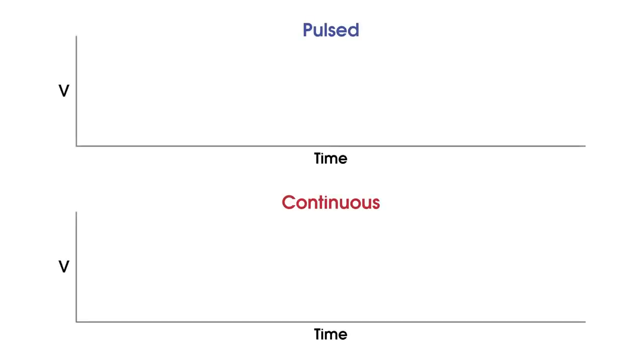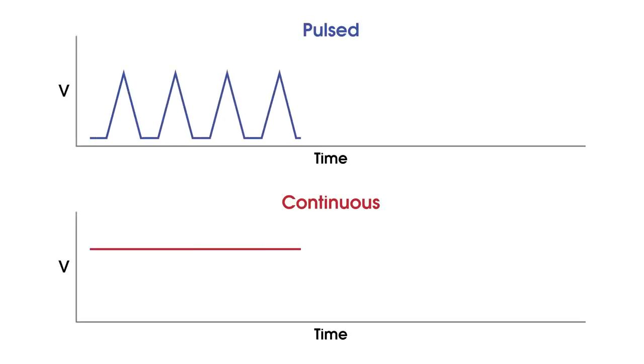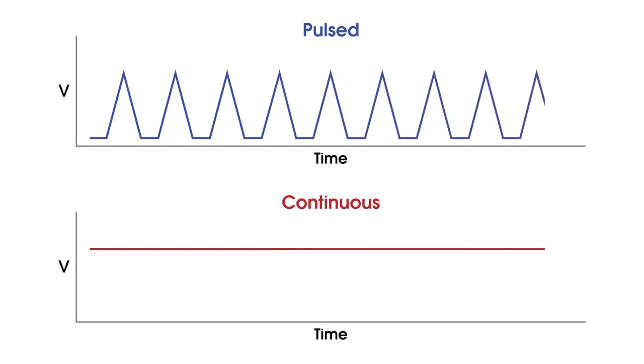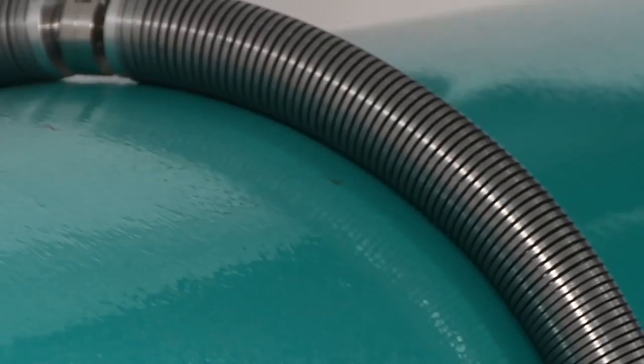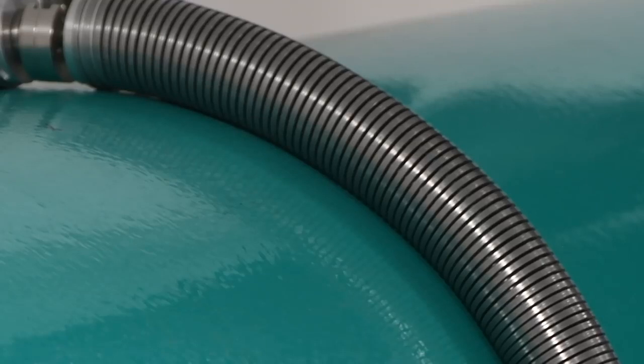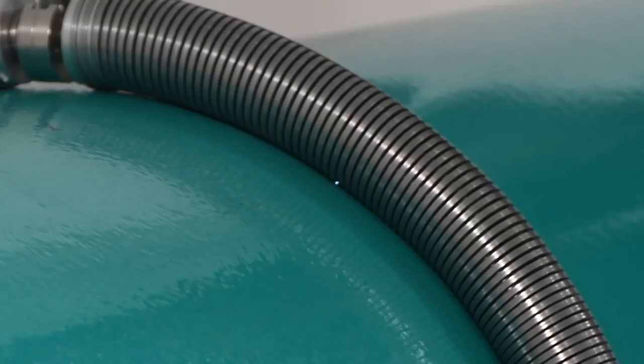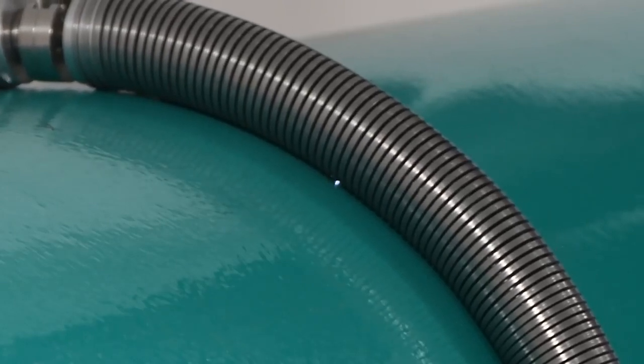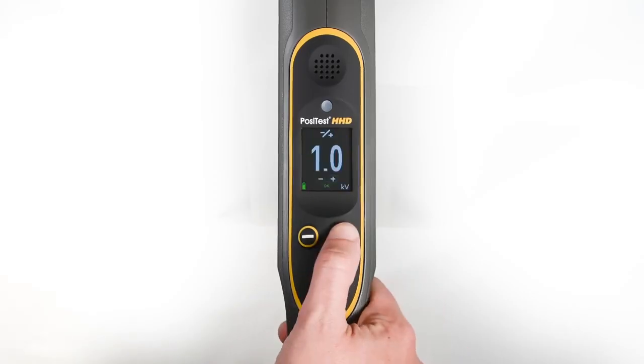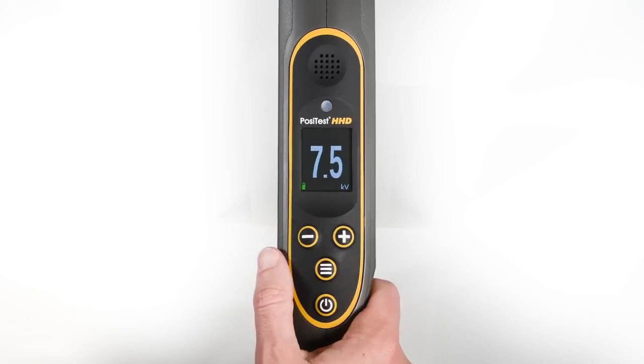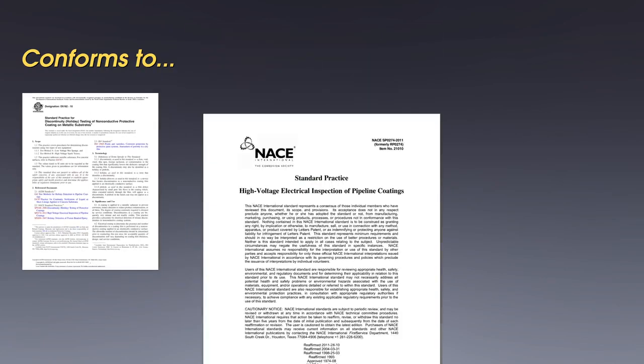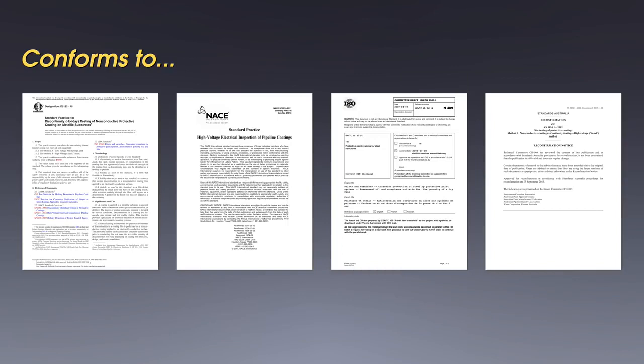The Positest HHD uses pulsed DC technology to detect flaws. Instead of a continuous high voltage output, the Positest HHD emits a precise pulse of high voltage 30 times per second. This technology is much easier to ground and safer, reducing the possibility of the exterior of the object becoming charged. The advanced circuitry is capable of maintaining a precise voltage output over the full range of 0.5 to 35 kilovolts in a single instrument. To alter the set voltage, simply choose the voltage selection menu option and use the plus and minus buttons to adjust. The Positest HHD conforms to ASTM, NACE, ISO, and ACA standards for holiday detection.